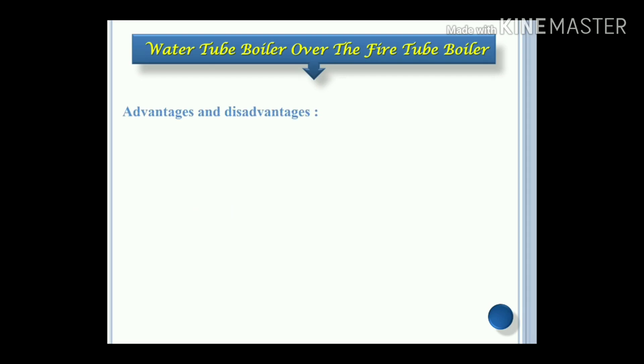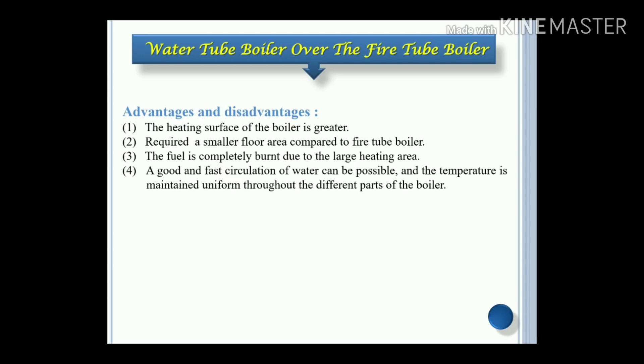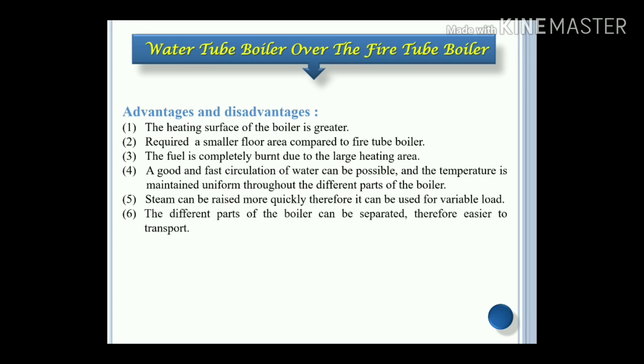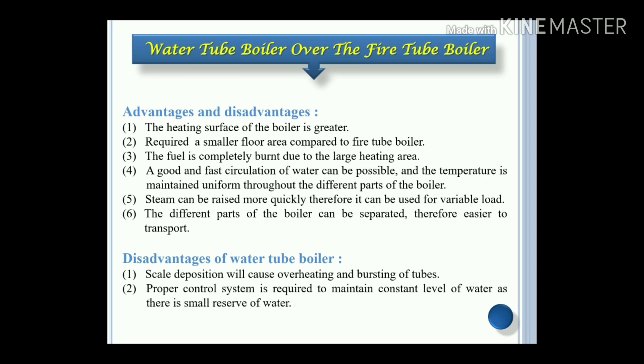Some of the advantages of water tube boilers over fire tube boilers: the heating surface of the boiler is greater, requiring a smaller floor area compared to a fire tube boiler. The fuel is completely burned due to the large heating area. Good and fast circulation of water is possible and the temperature is maintained uniform throughout the different parts of the boiler. Steam can be raised more quickly, therefore it can be used for variable loads. The different parts of the boiler can be separated, making it easier to transport. Disadvantages: scale deposition can cause overheating and bursting of the tubes. A proper control system is required to maintain a constant water level as there is a small reserve of water.